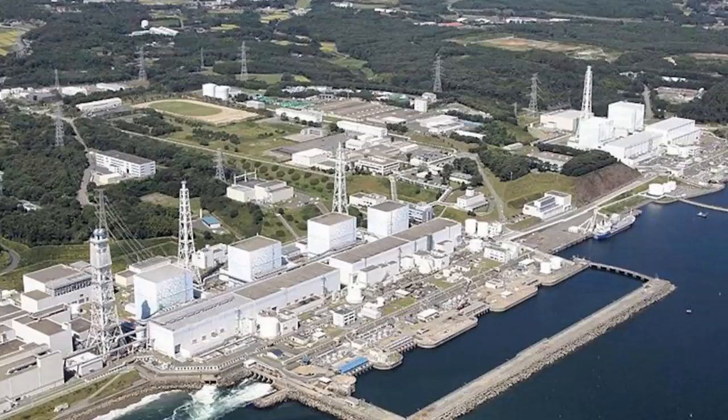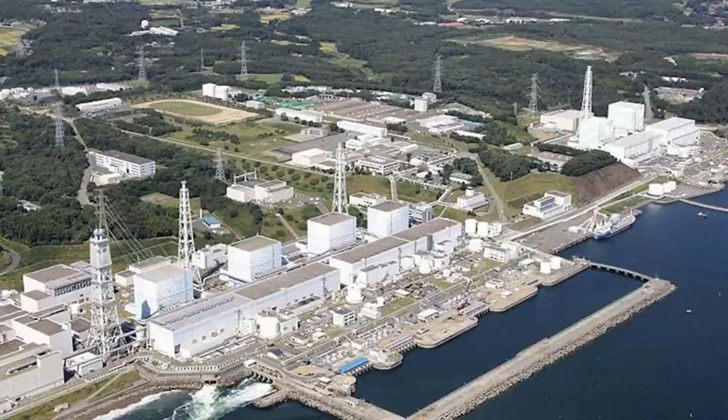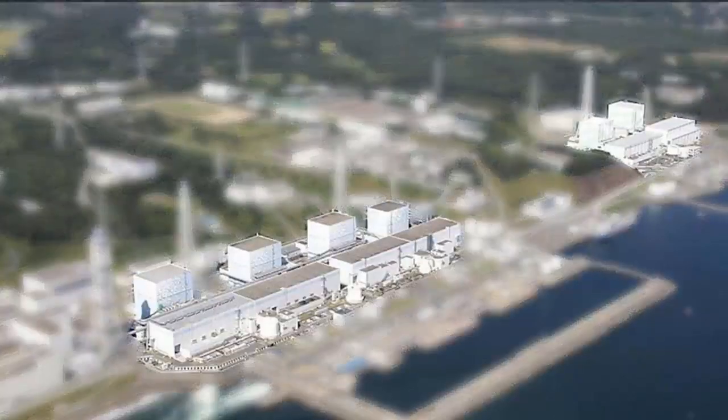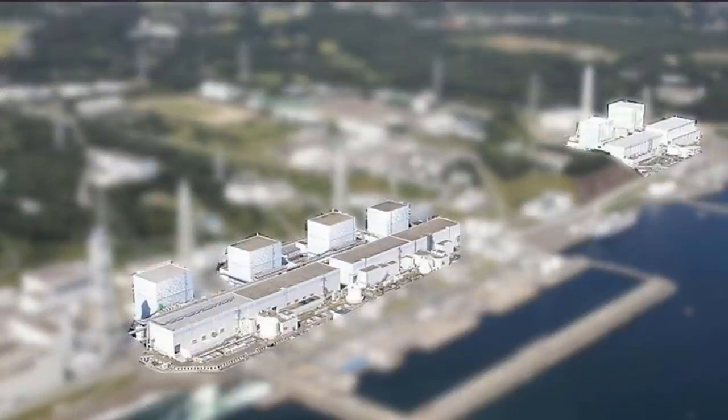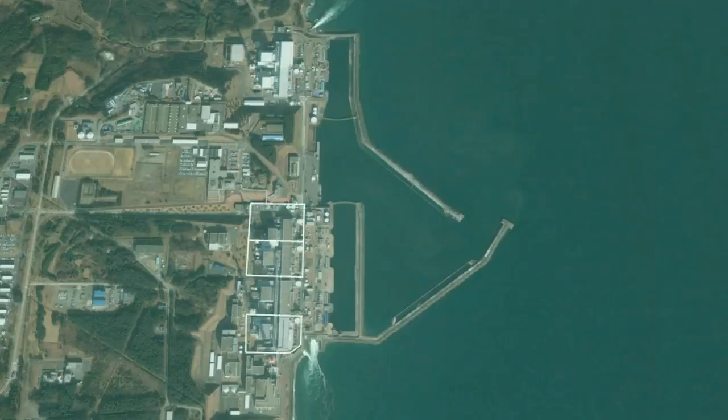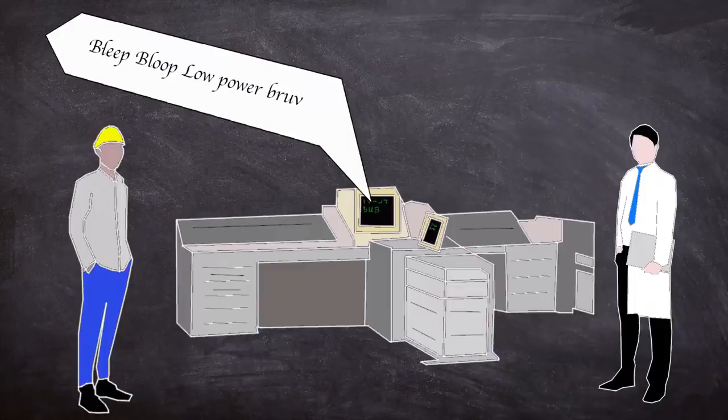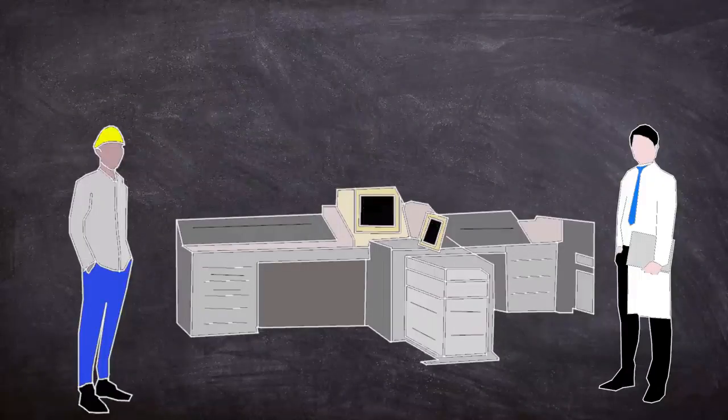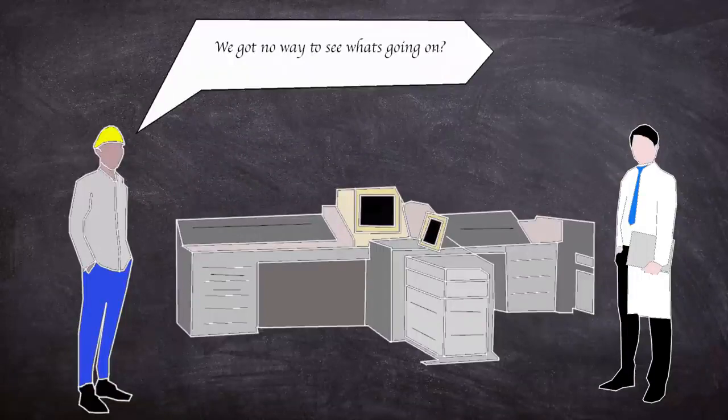One air-cooled generator survived and continued to supply emergency power to unit 6. This meant units 1 to 5 had total power failure. The power station was designed to work off DC batteries for up to 8 hours in the event of AC power loss. However, some battery systems were also affected by flooding. Power started to dwindle in units 1, 2, and 4 fifteen minutes post-flood. Operators of units 1 and 2 could no longer monitor reactor pressure, water levels, or key systems.